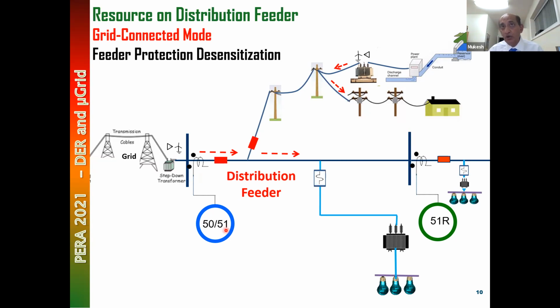Station protection has a local battery and is supplied by local backup power, so if there's an extended outage, the battery could last much longer. And there are alarms and all those things. This device is installed in the field. There may not be a good alarming system, and there may not be time to attend to them if there's a battery failure. But otherwise, for the purpose of this discussion, for the purpose of this presentation, we will consider the field recloser to be almost the same as feeder protection in the station.